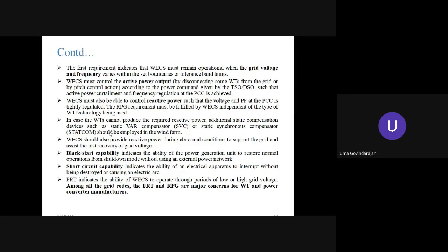In case the wind turbines cannot produce the required reactive power, additional var compensation devices like SVC or static synchronous compensator can be employed within the wind farm. So the reactive power control of the wind turbine generators helps to regulate the grid voltage. That is very important, because only if the grid voltage is regulated can we say that wind energy conversion systems must remain connected with the grid.